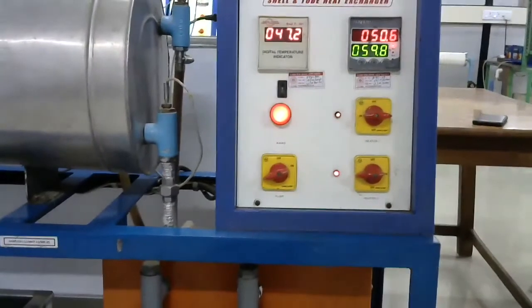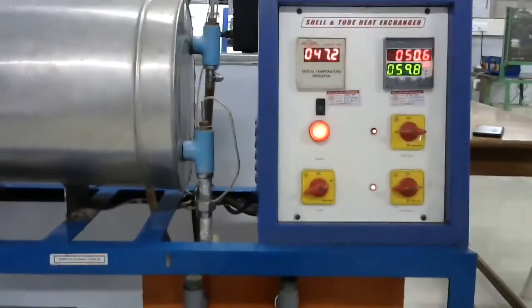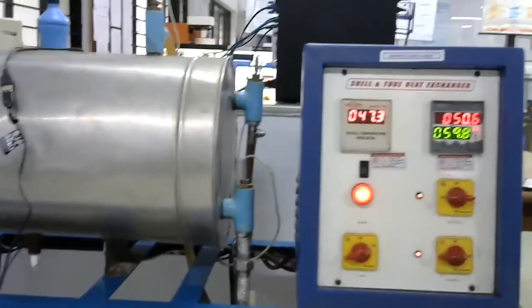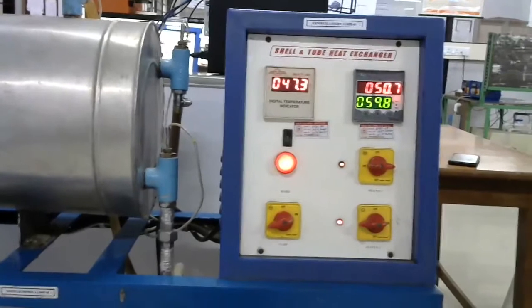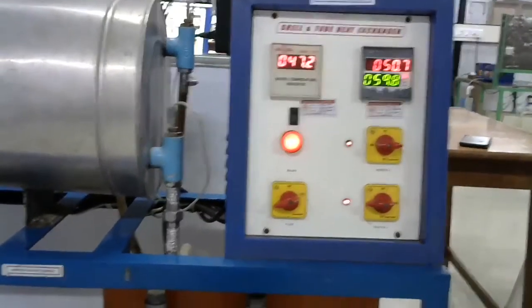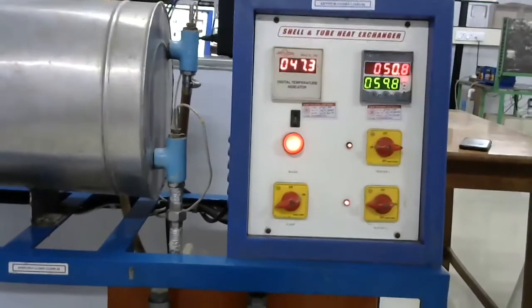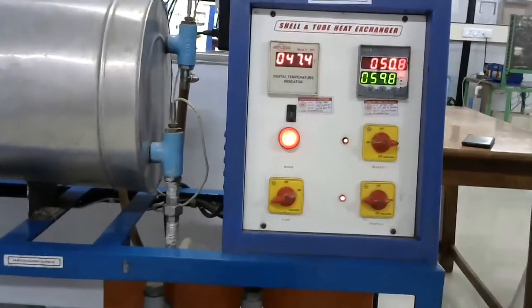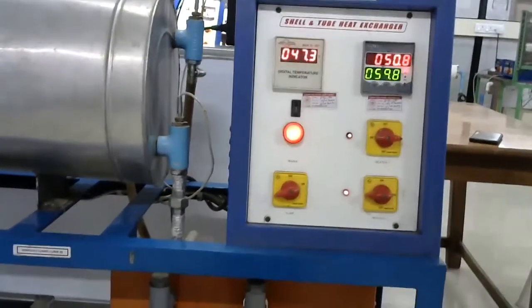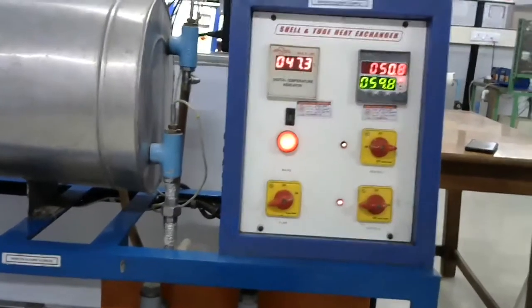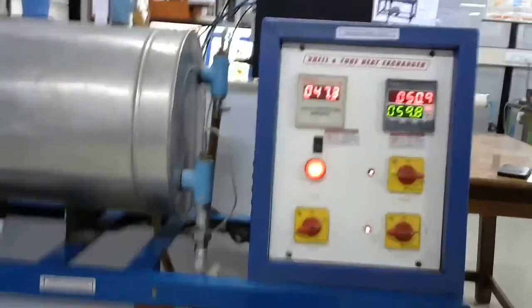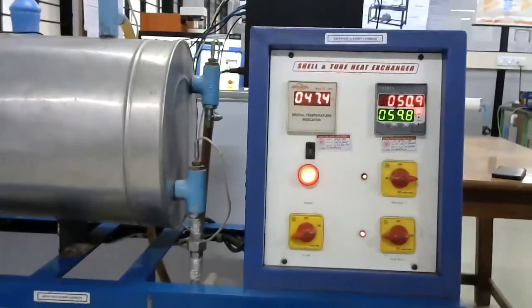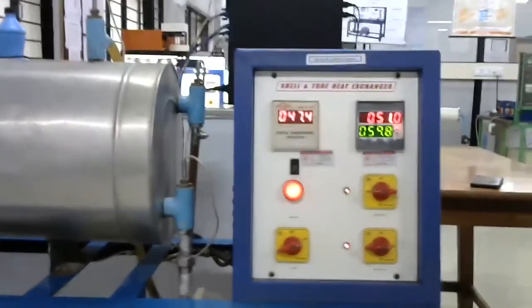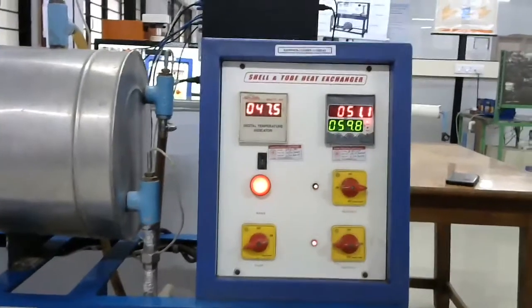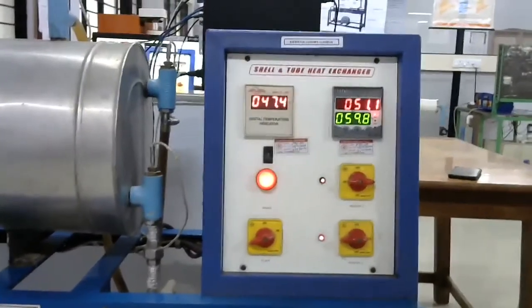Switch on the heater by operating the rotary switch given on the panel. Set the temperature of the water bath with the help of the digital temperature controller. Open the flow control valve and bypass valve for water supply. Switch on the magnetic pump for water supply. Adjust the hot water flow rate with the help of the flow control valve and rotameter, and then after reaching the steady state temperature, you can record the temperature of hot and cold water inlet and outlet after reaching the steady state temperature. So steady state temperature means when the temperature is not changing with respect to time, right?